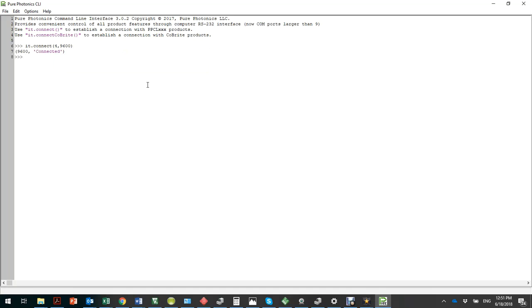The baud rate of most of our products — actually all of our products — starts at 9600. Of course you can set the baud rate at any rate you want. You can use the gen_config command to change that baud rate. Note that if you change the baud rate and you try to connect with this command, it will fail because the baud rate doesn't match what the unit has. For example, we can change the baud rate like this — this is the fast baud rate.